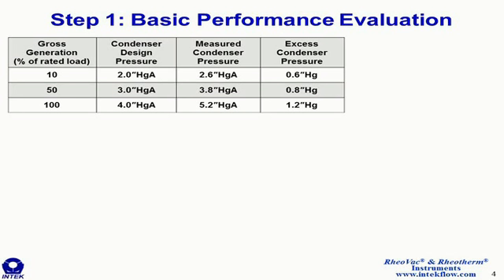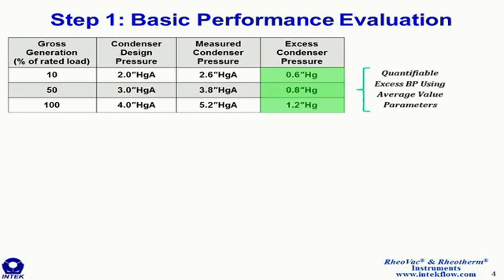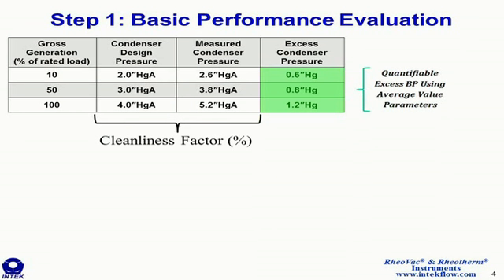So you might complete a table similar to what's shown on this slide. For example, at 10% of rated load, you might use those parameters to calculate a condenser design pressure of 2.0 inches, but the pressure gauge reads 2.6, so your excess is 0.6 inches. If you are doing the study at 100% load, you might get a condenser design pressure of 4.0 inches. The measurement might be 5.2, and so the excess is 1.2 inches. So all of this is available to you using commonly found measurements around the condenser, and it's quantifiable using average value parameter analysis. You can even use HEI methods to calculate a cleanliness factor, but that's all you can do.